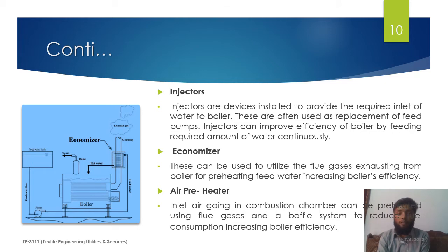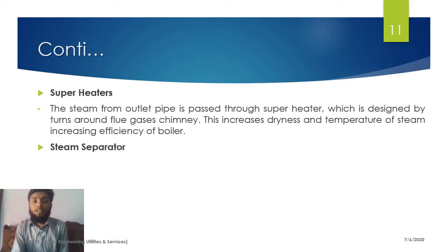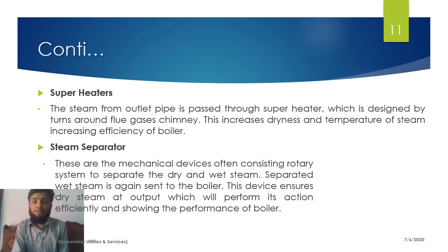The fourth accessory is air preheaters, also installed along the chimney, used for heating the air going into the combustion chamber. The fifth is a superheater — a device used for heating the steam going out from the boiler. The steam travels around the chimney in the superheater so that it is converted into dry steam.